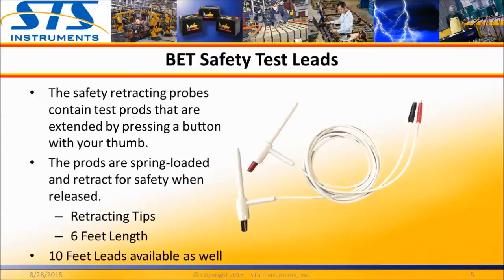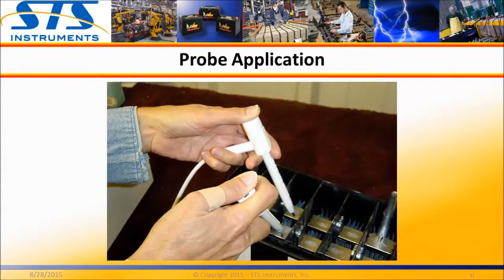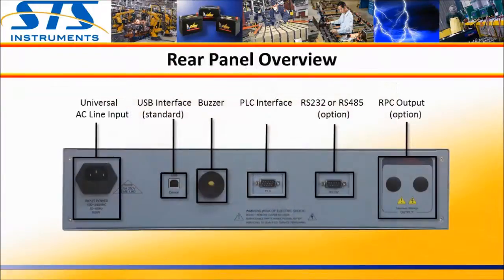To connect the battery element under test, a set of high voltage test leads with auto-retracting tips are included with each tester. These leads are the same as for previous generation testers. Standard leads are 6 feet long, but 10 feet leads are available as an accessory. This picture shows how to properly use the test probes to test the battery element. Note that both operator hands are required to ensure the operator cannot touch any exposed high voltage.